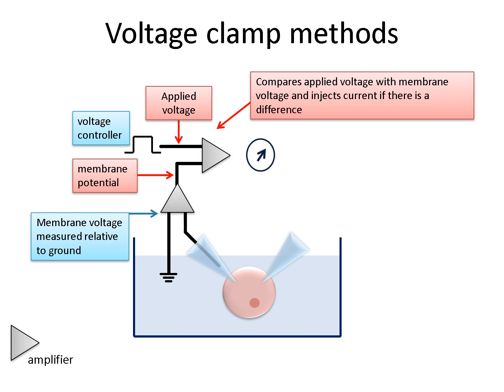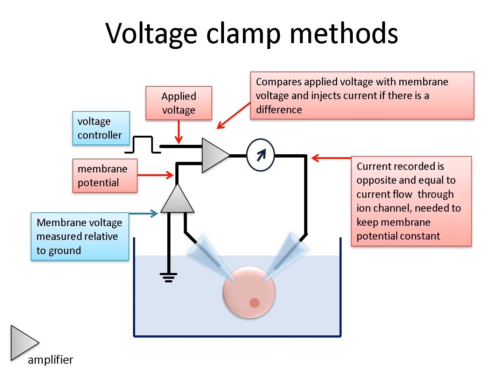The output of the amplifier is directed into the cell by a second microelectrode. If there is a difference between the membrane potential and the applied voltage, the microelectrode injects current, and this acts to change the membrane potential so that it matches the applied voltage. This current is the same magnitude as the current flowing through any activated ion channels, but is opposite in direction. So what is recorded is, in essence, the current that you need to inject into the cell to stop the membrane potential from changing in response to channel activation. And importantly, this happens on a very fast timescale so that there is an instantaneous injection of current as soon as any change in voltage is detected.